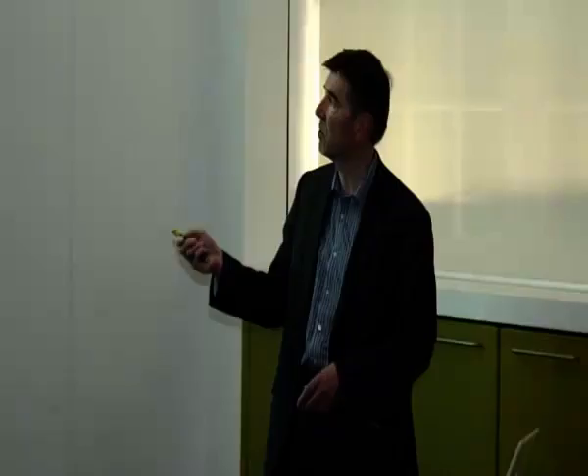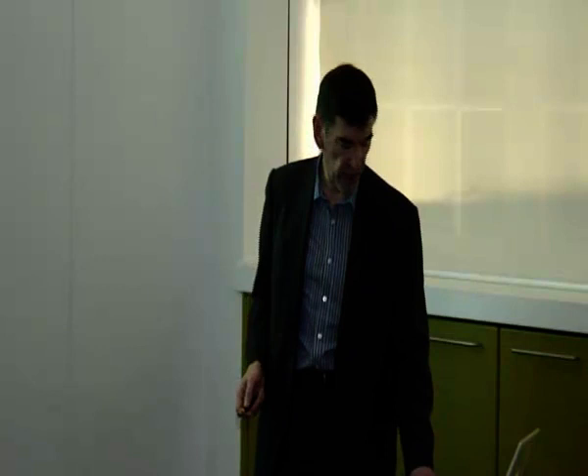This is one of the projects we took on as a very large footprint building because we couldn't go tall at all. We had a displacement system working in the middle and we wanted to understand how well that worked in conjunction with natural ventilation in the atrium and natural ventilation along the perimeter. Although you see a slightly different temperature here, it's still within the boundaries of where we had hoped it would be. When we looked at that in terms of a vertical section, we knew that the height would create a temperature gradient. We wanted to make sure it didn't result in too large a temperature gradient. We wanted to understand what having intermediate floor plates would actually do to that. What we saw gave us comfort that there wasn't a huge temperature gradient between the upper and lower floors, but nonetheless we introduced a small purging system for the top floor because the client had some concerns even after we'd done the modelling - so if it does get very warm up there, we could purge the heat out of the top level.